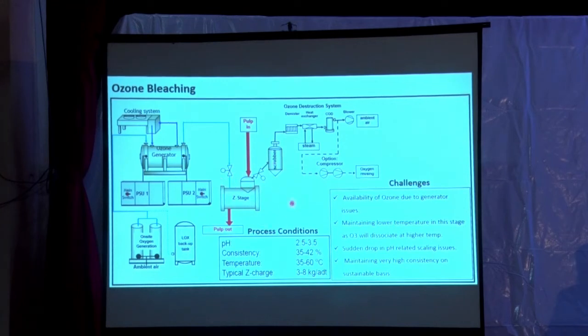Whatever slight unreacted ozone is there will be scrubbed, and the moisture separator will remove whatever water moisture is there, and the heat exchanger will maintain the temperature. Then it will go to the COD, catalytic ozone destructor, where MgO crystals are there. That will convert excess ozone into oxygen. Then finally it will go to the atmosphere.